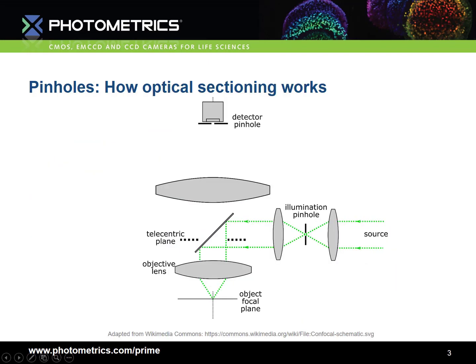The solution to this problem is to only allow light from our chosen focal plane to reach the detector. This is achieved through blocking light from other focal planes by placing a pinhole in the optical path. This is a so-called optical sectioning technique, meaning we are able to choose which vertical section of the sample we want to look at. The way this works is fairly simple. Light from our chosen focal plane will pass through the optical system and come to a tight focus within the aperture of the pinhole. This light will pass through to the detector.